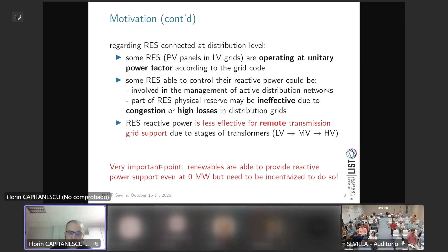Another important point, which is actually a positive of distributed energy resources, is that even if they don't produce active power, as long as they're connected to the grid they may still produce reactive power. However, for now, they are not incentivized to do so. That's something that could change.